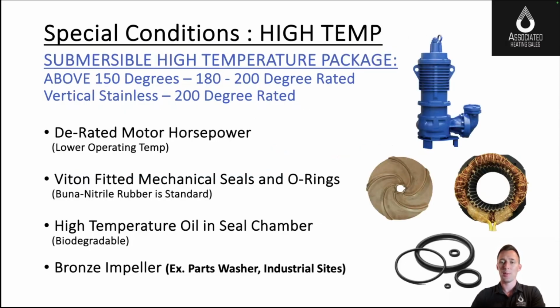We get this question about a high temperature system often. So anything above 150 degrees, you may want to start to think about a high temperature package from Weil Pump. If you want the highest rated pump in the submersible pump category, an all stainless steel pump would be the best. Unfortunately, all stainless steel pumps are 4 times the cost of a cast iron pump. And we'll look at that in a second as well. But there is a go-between option.